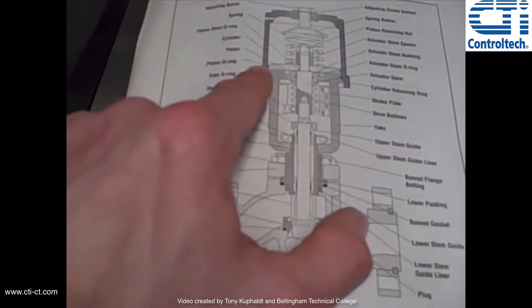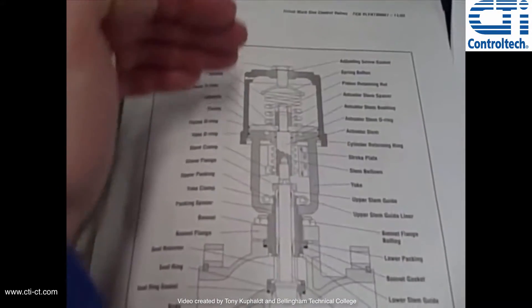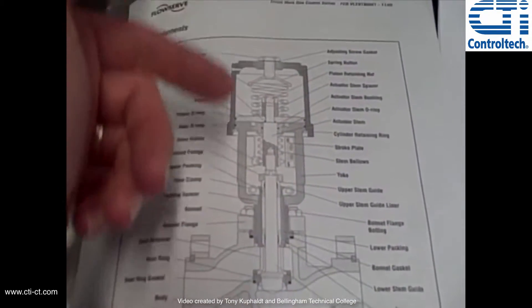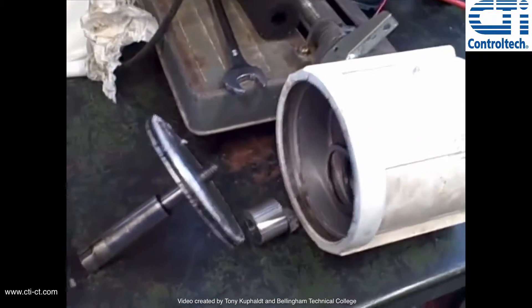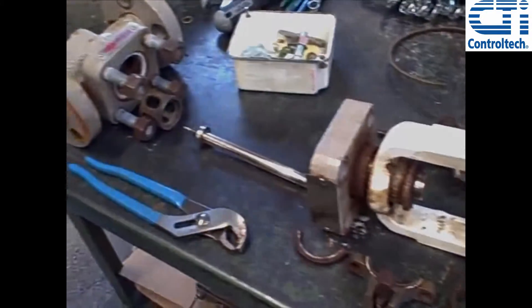Looking at the documentation, here's a document showing the valve body, the yoke, and the actuator — and it's a piston again. It goes up and down, and that's what establishes the motion of the valve. So we've got ourselves a piston-actuated globe control valve, in this case made by Valtek. It is a Mark 1 model valve.